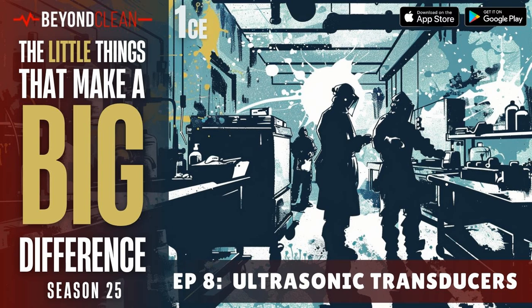Now, I'm no scientist, Pawel, but I'm going to do my best to try to summarize this in one go, so you can let me know if I've got it. So we've got a generator that produces high voltage electricity that is sending this electrical current to these transducers that are fixed to sometimes the outside of the tank, and they're what are converting that electrical signal into some kind of mechanical sound wave into the cleaning solution to create the cavitation. Is that what we're talking about? Exactly. So the piezoelectric element of the transducer contracts and expands, and it's pushing the mass that is attached to it. Then that vibration is transferred to the side or the bottom of the tank, typically.